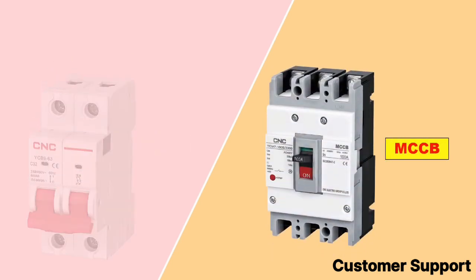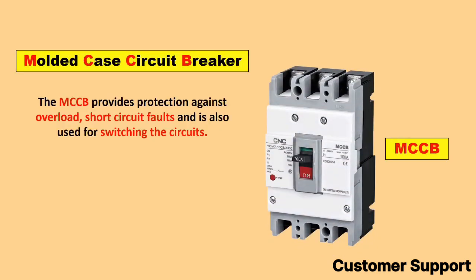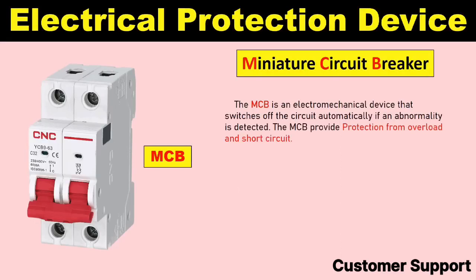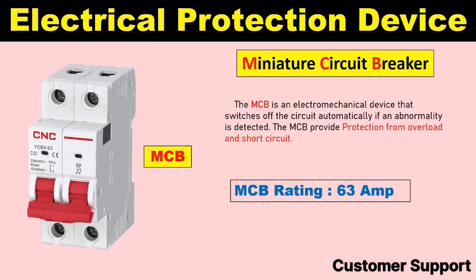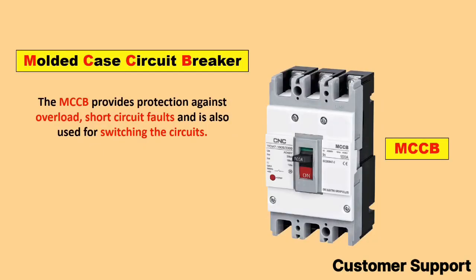After this, next device is MCCB. Full form of MCCB is molded case circuit breaker. Friends, the MCB you have, or if you are going to buy a MCB, then a maximum of 63 ampere rating MCB you can buy. These days you can find a 100 ampere rating MCB also, but before, till 63 ampere rating MCBs were available in the market. Now if you want a protection device of even higher rating, then in this condition you have to buy a MCCB. MCCB also provides protection from overload and short circuit.